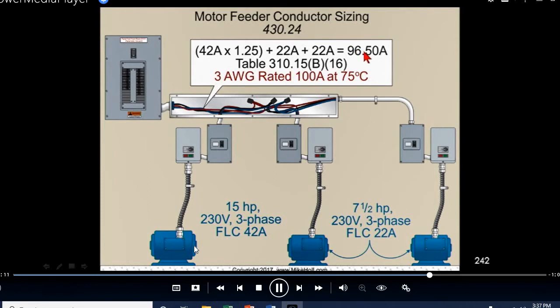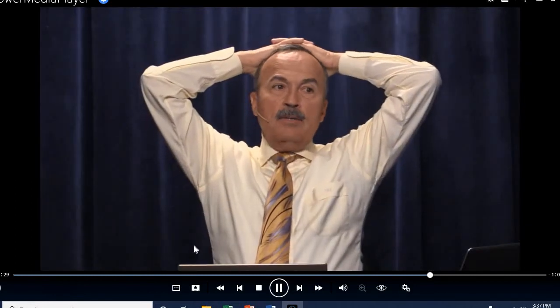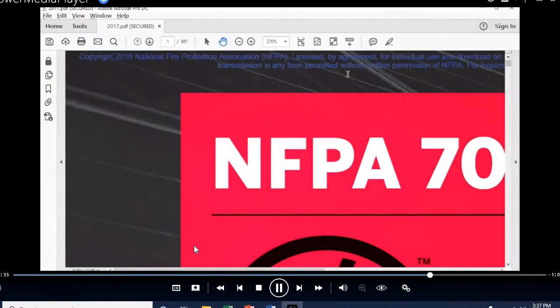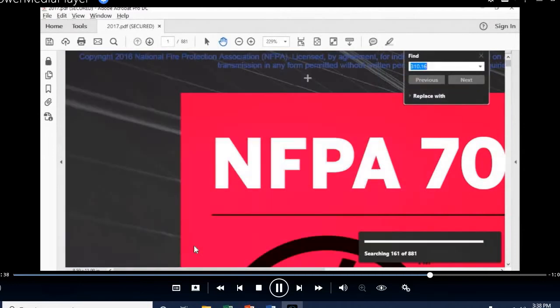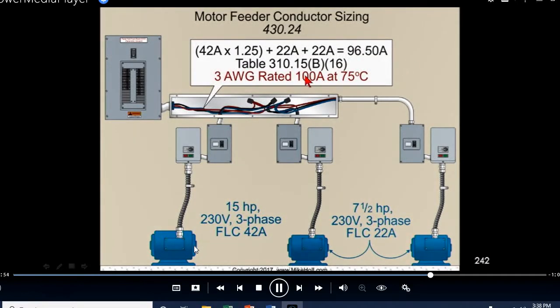I'm going to round this off. However, Mike, let's start rounding this off. We'll start making this 97. In our textbook, we start rounding it off. 97. Have to find a wire that's rated 100 amps at, ooh. You're right. Size the wire at 75 degrees C terminals. So 310.16, go to the code book, look it up, go to the 75 degrees C terminal. Number 3. Okay, without me having to go through it and find it again, it is a 3-gauge wire at 75 degrees C. And that's how you size it.